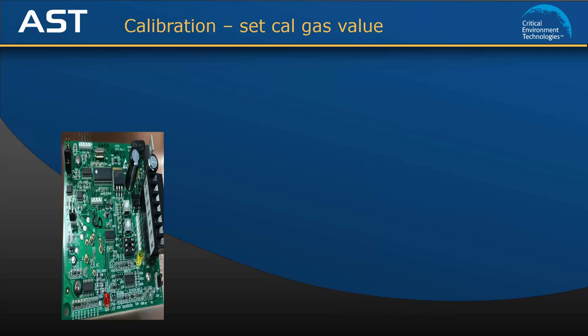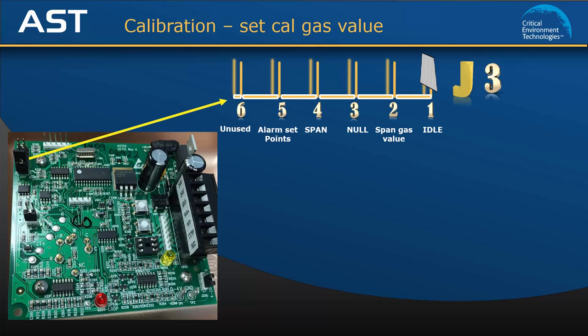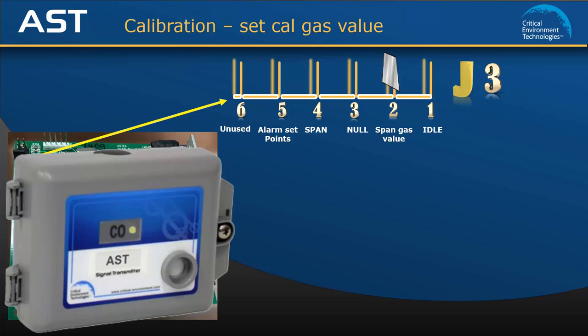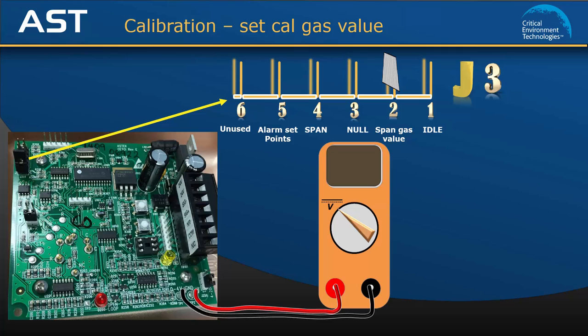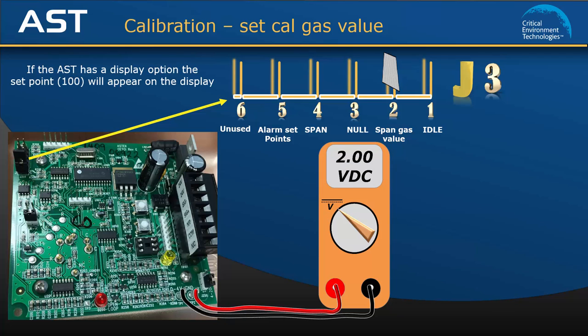Open the AST and find the jumper bank on the left side of the board. Move the jumper from the idle position to position 2, span gas value. The green LED light on the outside of the enclosure will flash once to confirm that it is ready for you to set the calgas value. Attach the voltmeter leads to test points TP1 and TP2. Use the up and down push buttons to adjust the number to the calculated voltage reading on the multimeter, which is 2 volts in this exercise. If the AST has the optional display, the display will read 100 ppm. To complete the set calgas value procedure, move the jumper back to the idle position. The new value will be saved and the LED will change back to solid green.